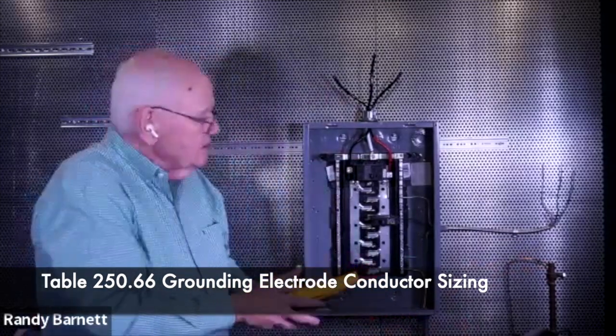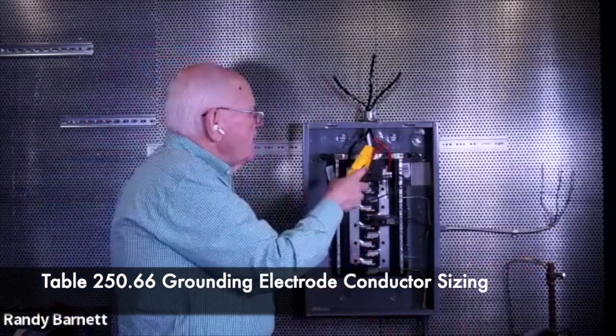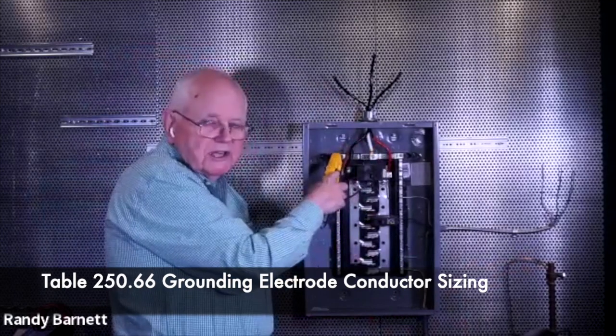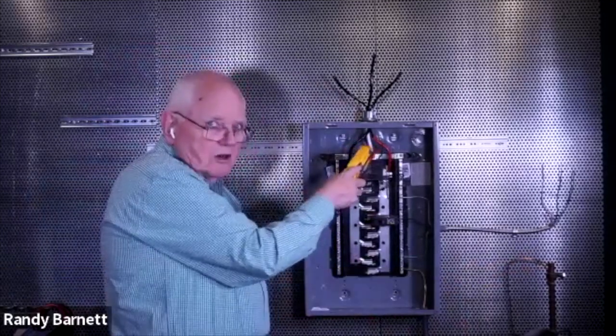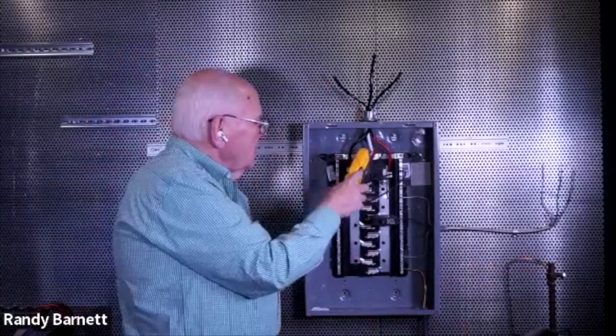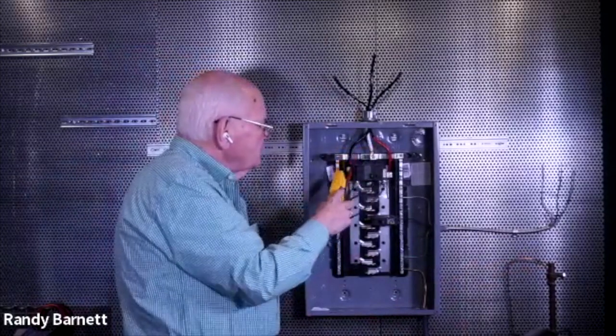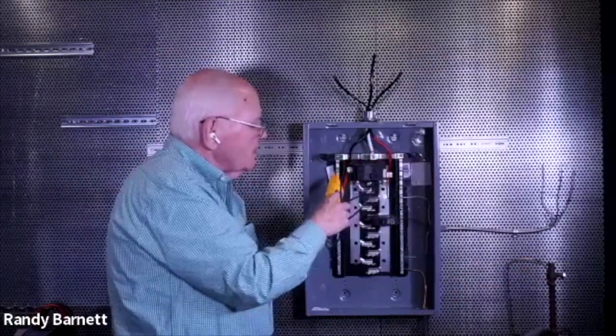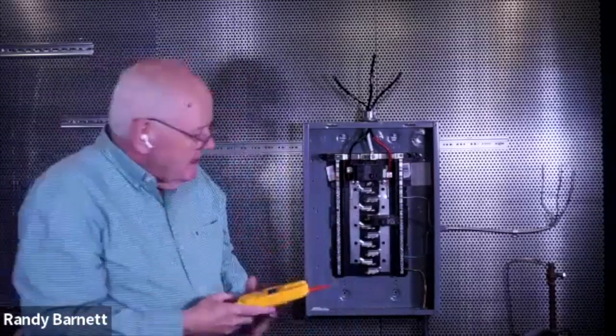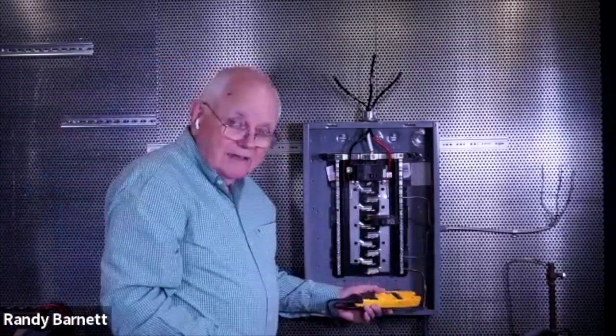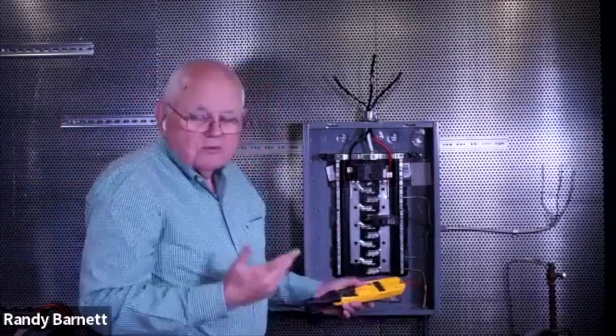So my table tells me that for 2 AWG or smaller, and these are 4 AWG, so they're smaller than 2 AWG, it says that for the 4 AWG conductors coming in for this 100 amp service, if I use copper, my grounding electrode conductor can be an 8 AWG, a number 8 in other words, going to my grounding electrode. Pretty simple table.